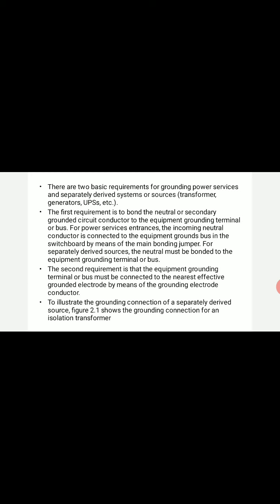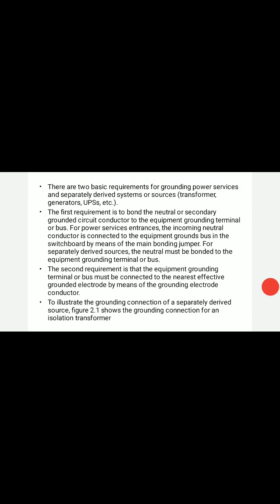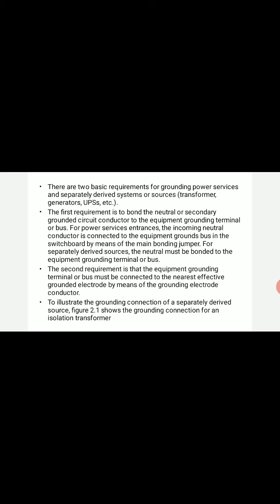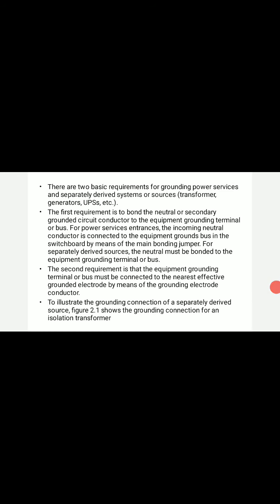The second requirement is that the equipment grounding terminal or bus must be connected to the nearest effective grounded electrode by means of a grounding electrode conductor. To summarize, the two basic requirements for grounding power services are: first, bond the neutral or secondary grounded circuit conductor to the equipment grounding terminal or bus; second, connect the equipment grounding terminal or bus to the grounded electrode by means of a grounding electrode conductor.